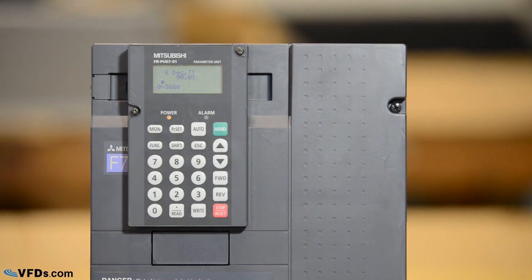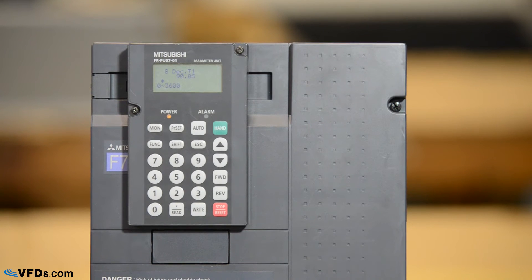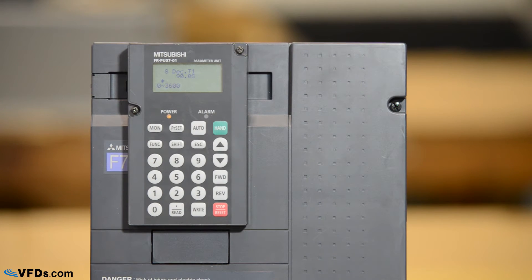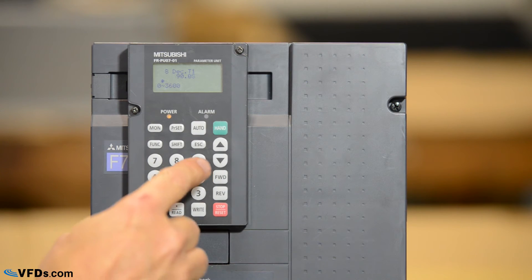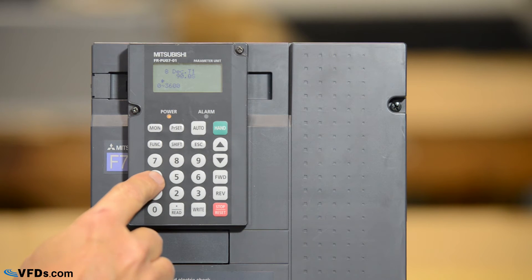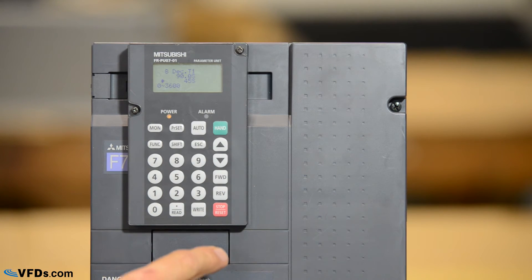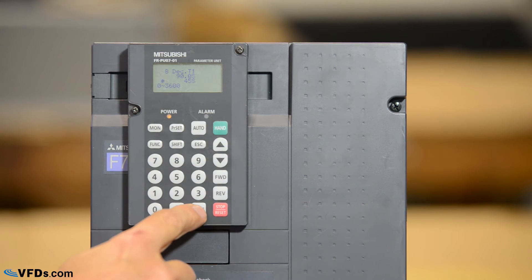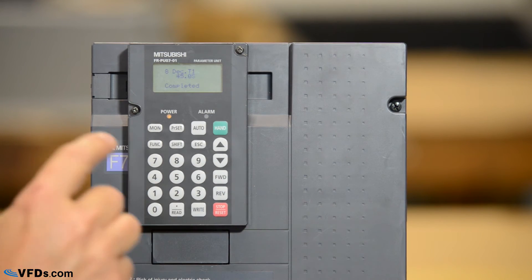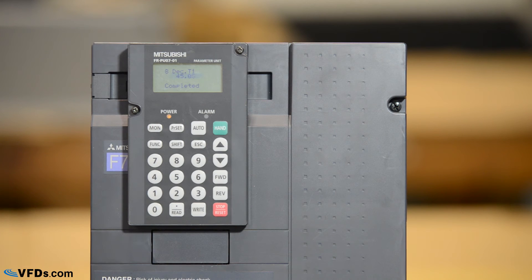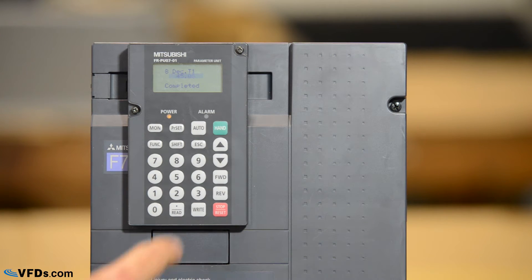Pressing shift again we get to parameter eight. It's set for 90 seconds. I think we can go a little quicker than that. Let's set that for 45 seconds. Typically the deceleration time is slower than the acceleration time.